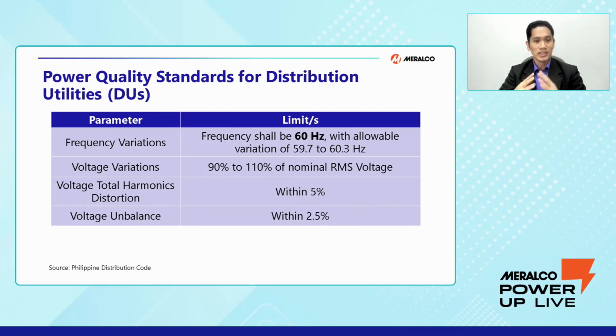For the voltage variation, it is 90 to 110% of our nominal RMS voltage. Meralco has several service voltages available. For secondary voltage, we have 230 volts, 400 volts and 460 volts. For primary metering, we have 13.2 kV, 13.8 kV and 34.5 kV. It depends on the location where our facilities are served by a utility like Meralco. For large industrial and commercial customers of more than 10 MVA, we could serve them from the 69 kV or 115 kV sub-transmission grid.